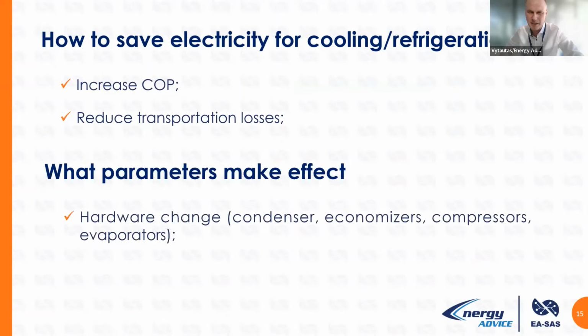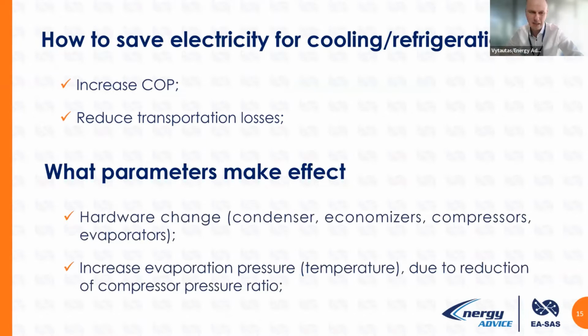What parameters could have an effect? So, hardware change we discussed, and probably the best solution is to increase evaporation pressure or temperature. Why? Because it reduces the compression ratio, and if we reduce the compression ratio, the compressor would operate at better efficiency. Compressor by itself, better efficiency. So hardware change is a costly solution, so we should somehow manipulate evaporation pressure in order to have a better compression ratio.